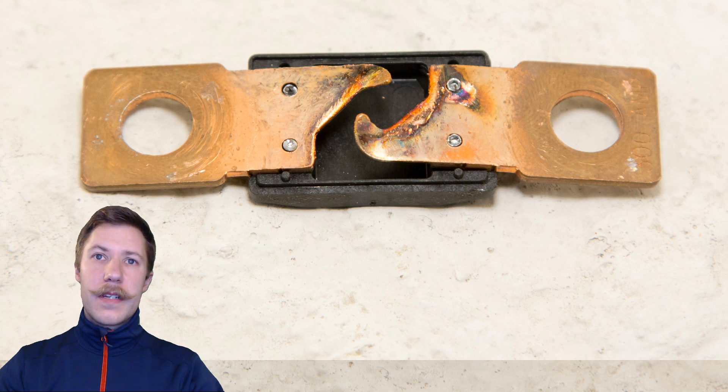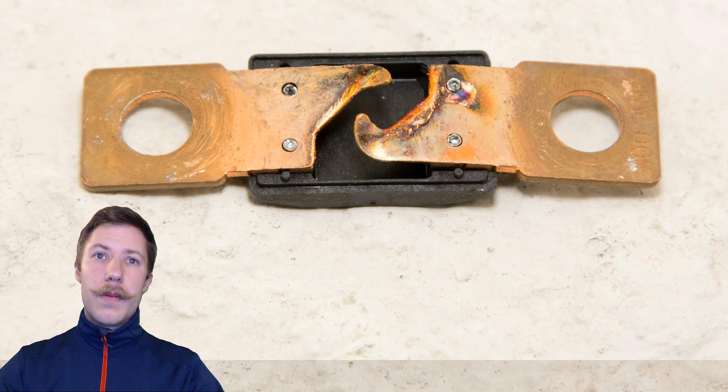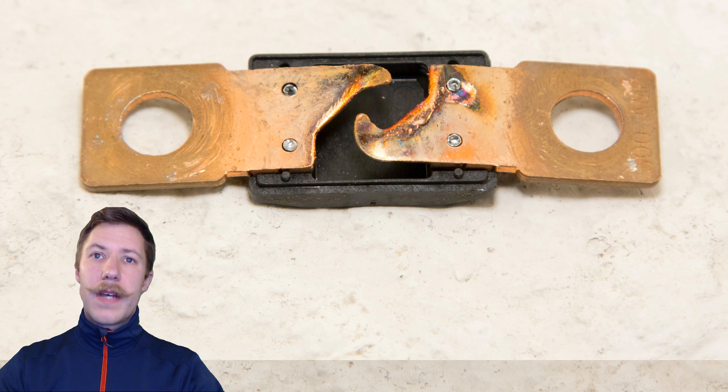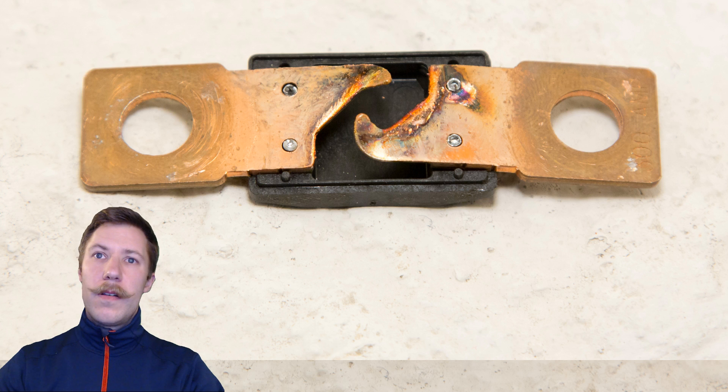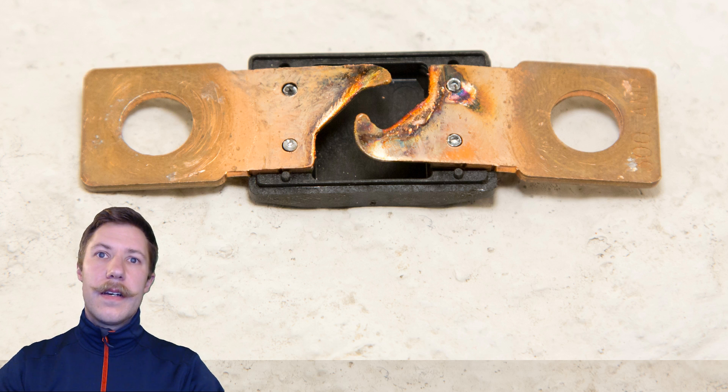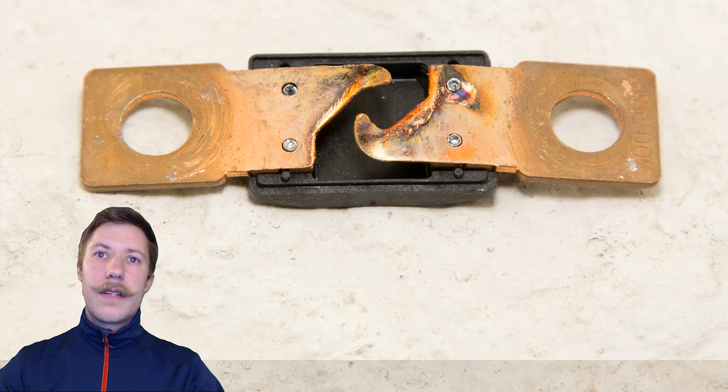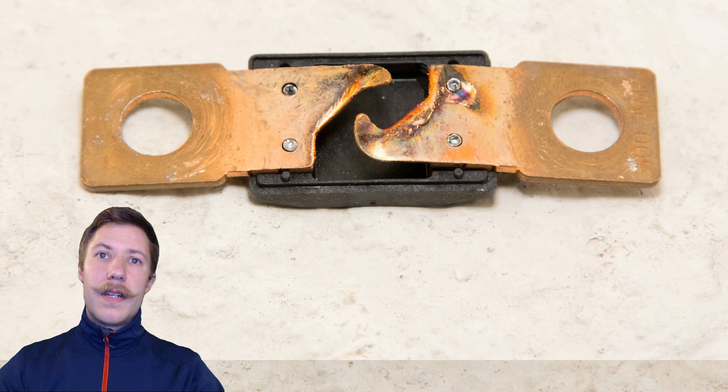As you can see here the damage to the 300 amp DC fuse is quite substantial. Copper is a really poor material when we have to do with arc flash currents. All the edges here and the pointy parts of this fuse element is completely melted and all round now.